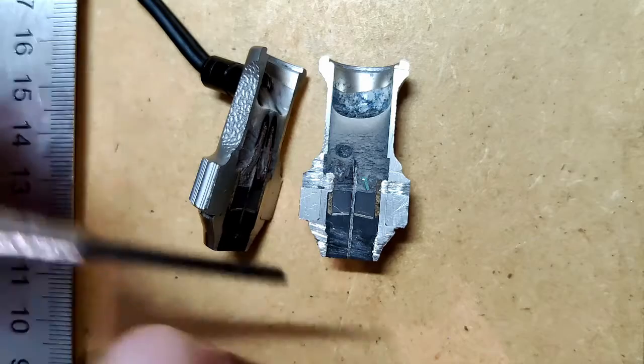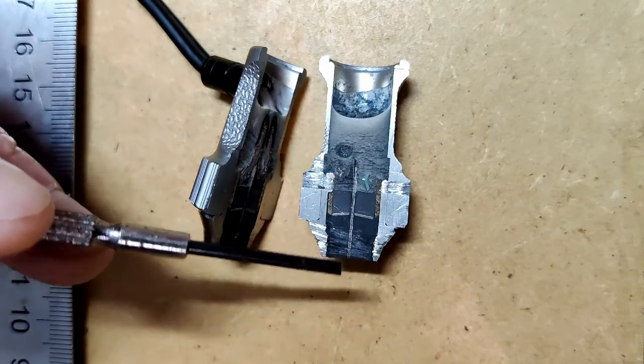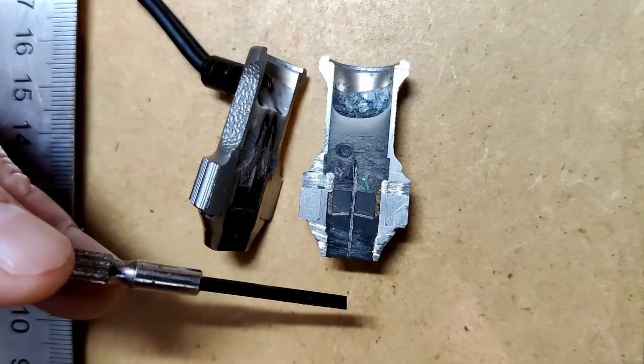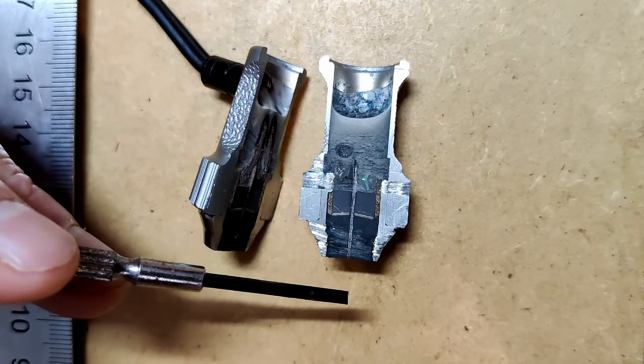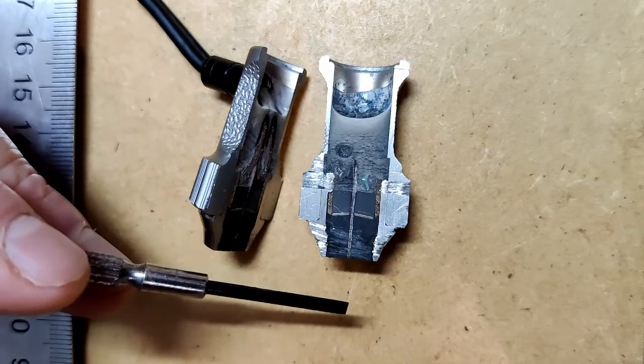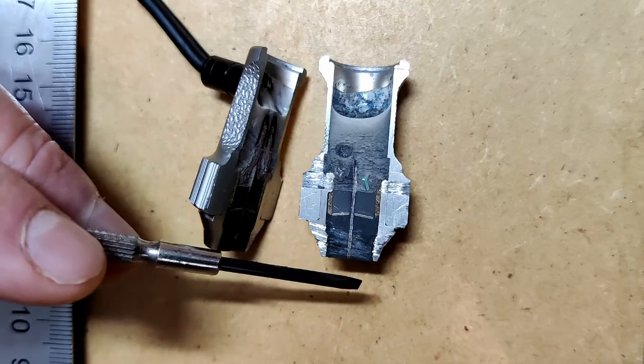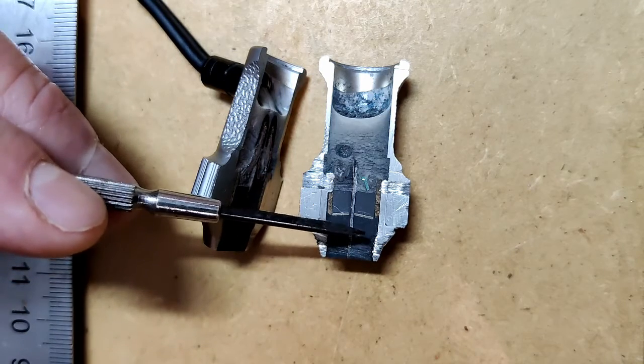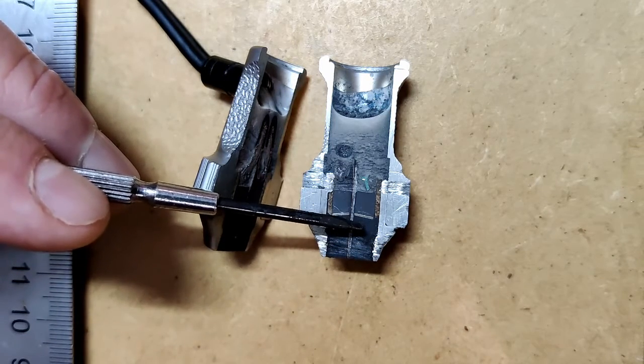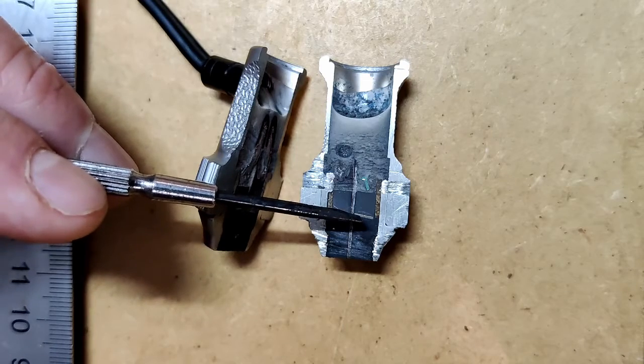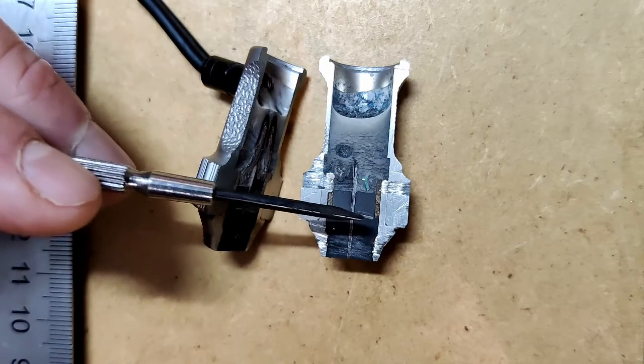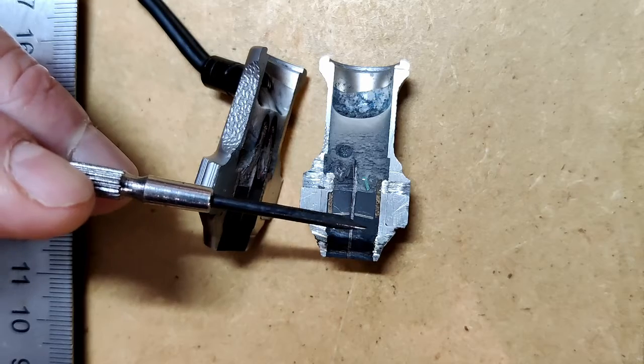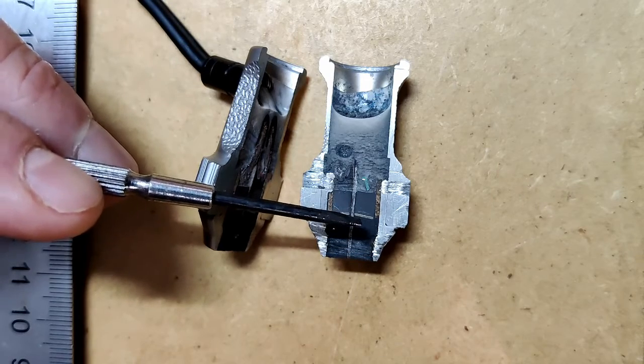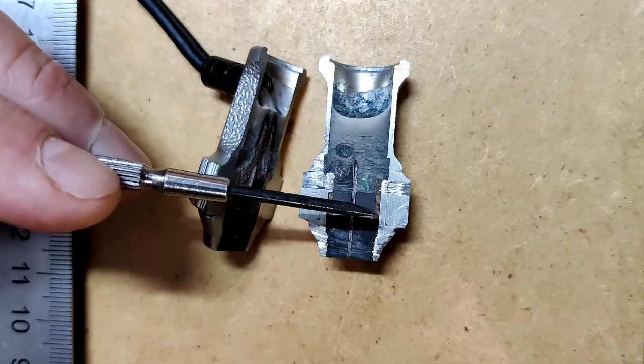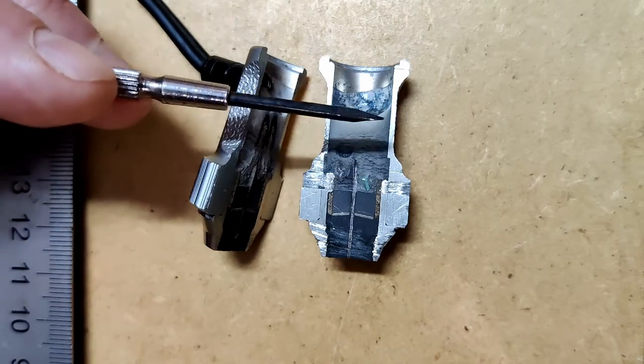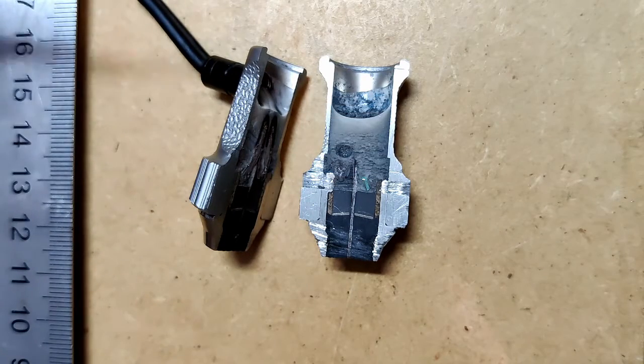Once it enters the component, the idea is we will go through the material until we either hit a flaw or an indication or the back wall, and then that sound will actually bounce off that and return back up to the received crystal. The equal and opposite happens in this case, where the received crystal will be mechanically vibrated by that sound energy, and it will transfer that back into an electrical pulse, which is what we'll see on our screen.